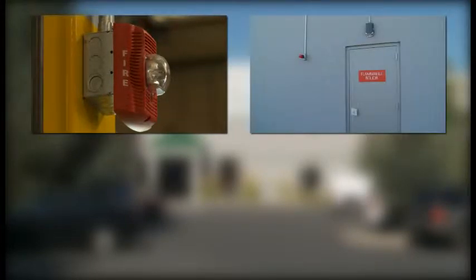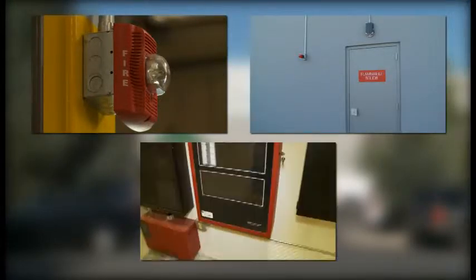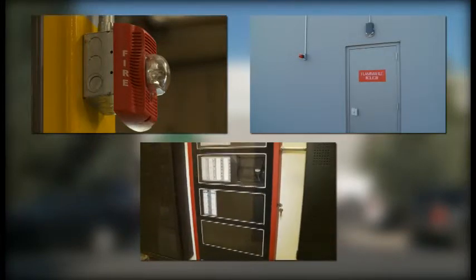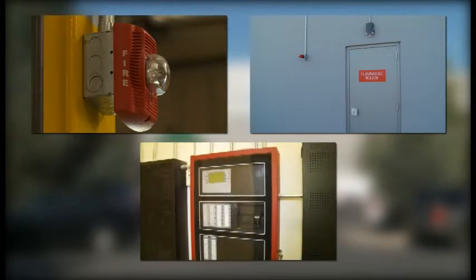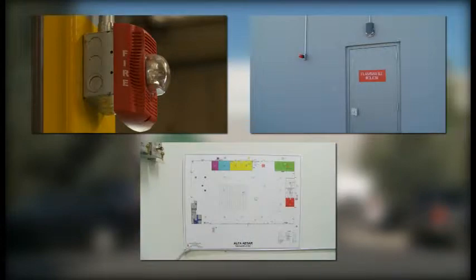The building is equipped with strobe and horn strobe appliances. Beacons located outside the exterior doors to each storage area indicate which space is in alarm. An annunciator is located in a dedicated fire alarm control room adjacent to the main lobby entrance, with a graphic directory adjacent to it.